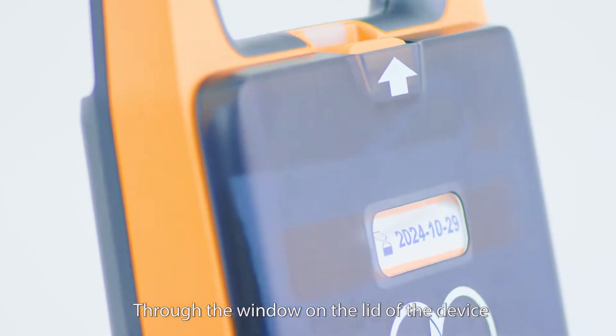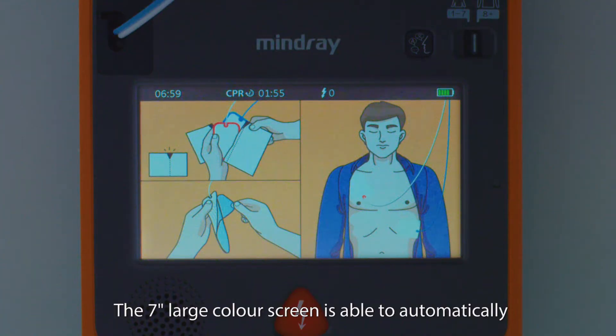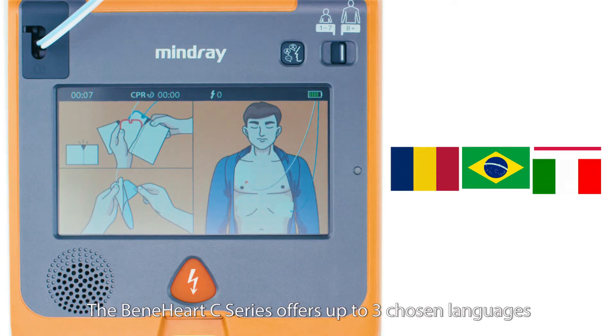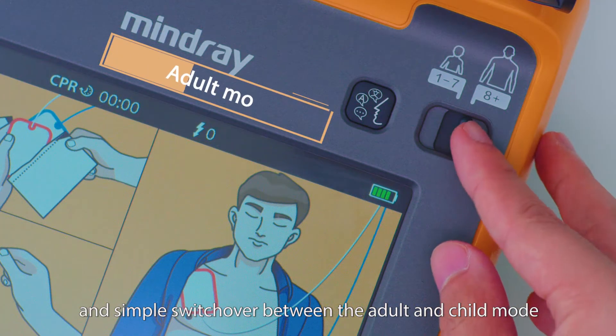Through the window on the lid of the device, users can check the pad's expiration date. The seven-inch large color screen is able to automatically adjust screen brightness to different environments. The BeneHeart C Series offers up to three chosen languages and simple switchover between adult and child mode.